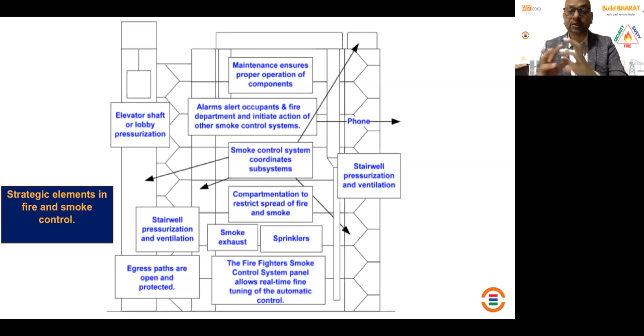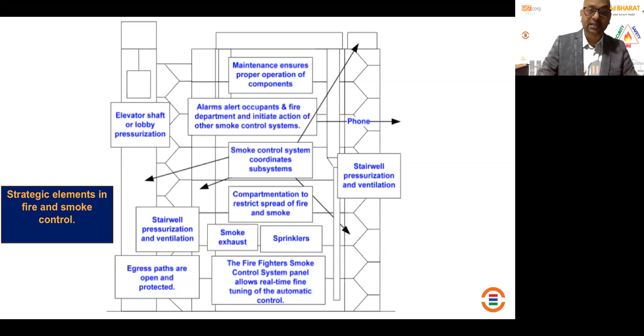Because we have seen in the past, there have been many incidents where fire officers themselves have been the victims. Because there was no smoke management system in the building, they didn't know how and when to enter. There was no oxygen available, the smoke was trapped, and they were trapped in the building. So this communication is going to help the fire rescue people. If you have that integration done, they can actually identify which fan to switch on, which zone is safe, which zone is not safe. And your sprinkler system sequence has to be such that it operates based on your cause and effect diagram. So this is what the entire smoke management is all about, which has to be engineered.